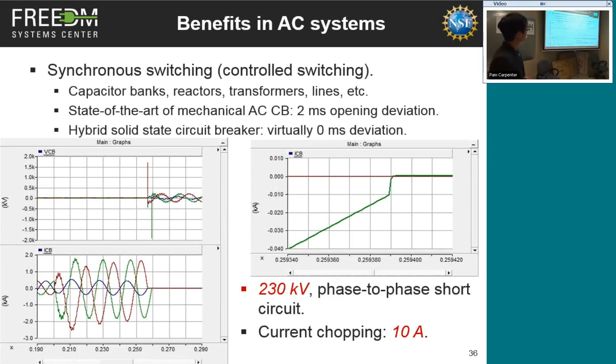There's also something called synchronous switching, sometimes called controlled switching. In an AC system, when you switch an equipment on and off, for example a reactor, a capacitor bank, a transformer, or even a transmission line, you actually want to switch the circuit at some exact moment to reduce the transient caused by the switching operation.